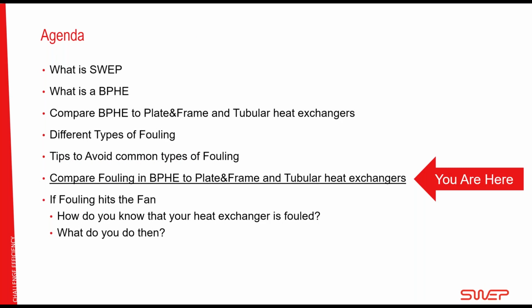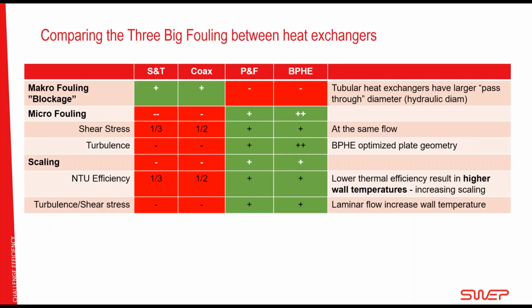Wow, a lot of words here, right? So where are we now? We are to compare fouling in the brazed plate with the plate and frame and the tubular heat exchangers. So if we now look at the four types of heat exchangers, shell and tube, coaxial, plate and frame, and brazed plate, and look at the macro fouling, who is the winner here? Well, it's actually shell and tube and coaxial. Why are they the winners? Due to the plate and frame and the brazed plate heat exchanger, we have the small hydraulic diameter, or so to say the small distance between the different plates. A shell and tube or coaxial will be able to swallow a bigger stone, right? The pass-through diameter is absolutely better here.